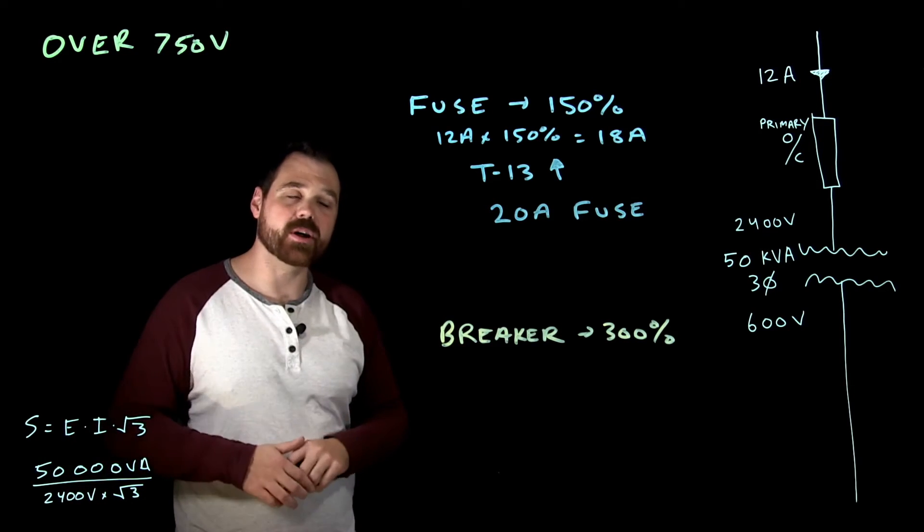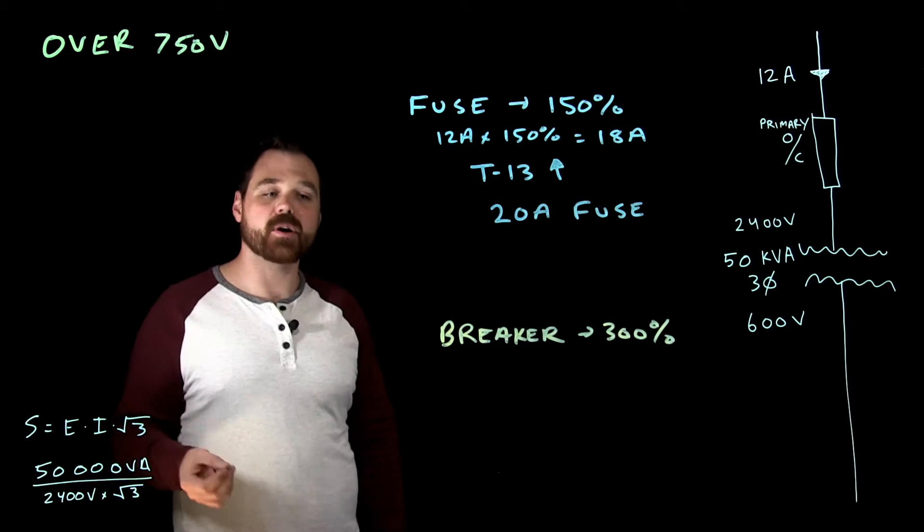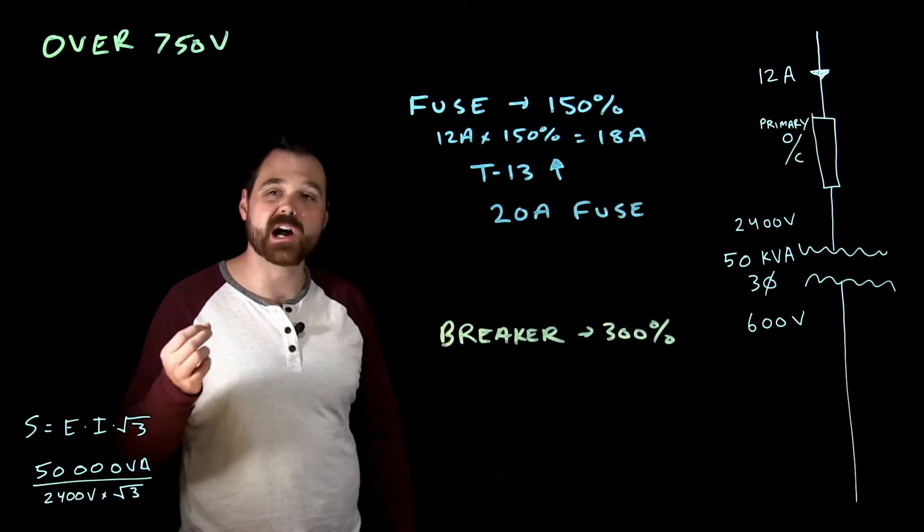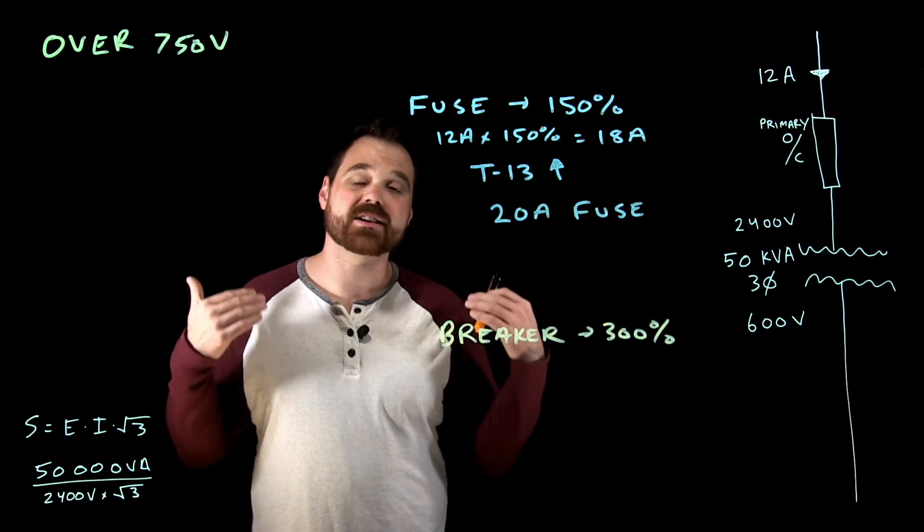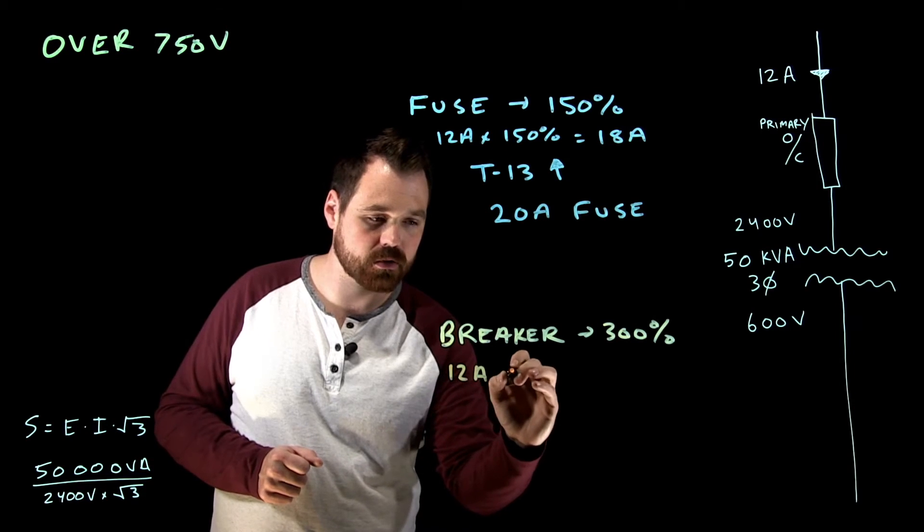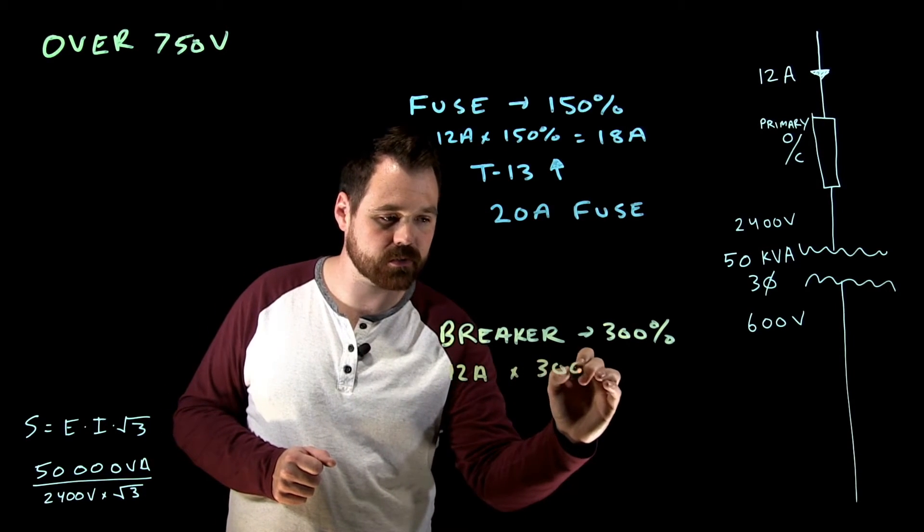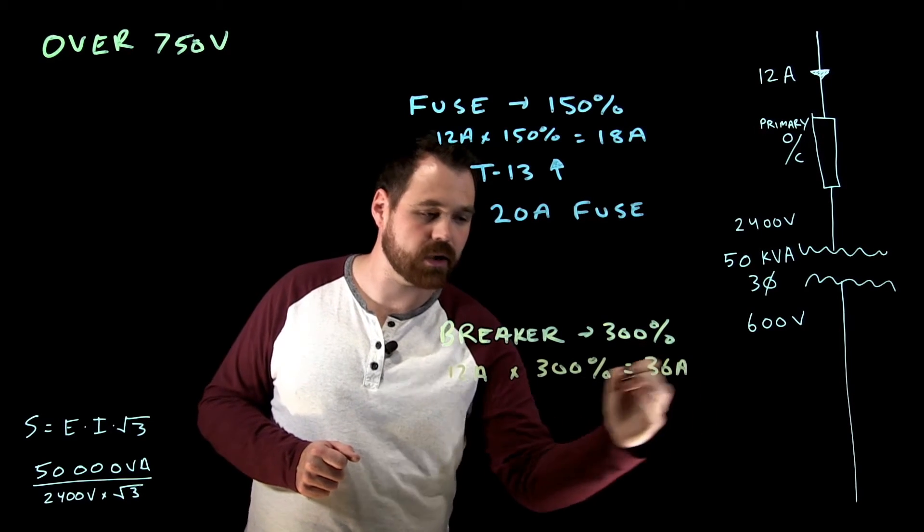Now with a circuit breaker, same rule we're dealing with, but it says that my circuit breaker shall be based upon 300% of the rated primary current, and it says it shall not exceed. So in this case, we are going to take our 12 amps times 300%, which gives us 36 amps.